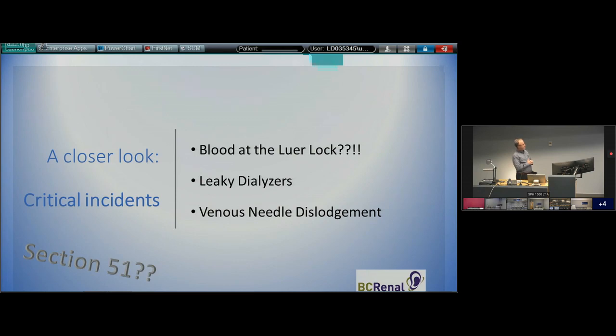For those of you not hemodialysis oriented, in hemodialysis we run blood through a filter, and on the other side of the filter there's non-human fluid. Yes, they're supposed to diffuse and osmose and UF stuff across the filter, but they're not supposed to actually break and mix directly. The machines have sensors that can tell you when the dialyzer membranes crack or break, and that happens every now and then. But every now and then is like every now and then - that's not a common thing.